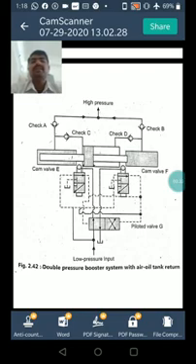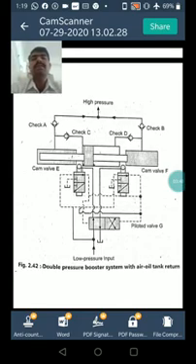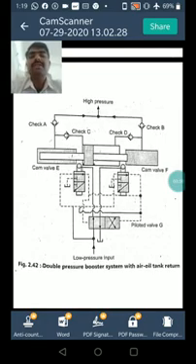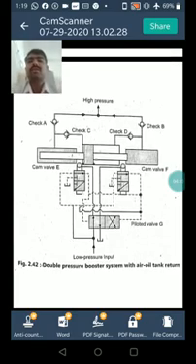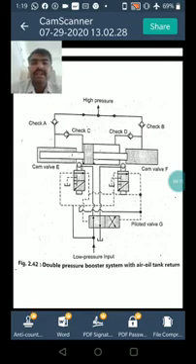Okay, in this figure a typical air oil intensifier is shown. The cylinder travels a long distance at low pressure and a short distance at high pressure to complete the operation of work. Then valve A is used to extend and retract the work cylinder at shop air pressure. Valve B applies shop air pressure to the head end of an air cylinder to drive a booster cylinder at hydraulic pressure.